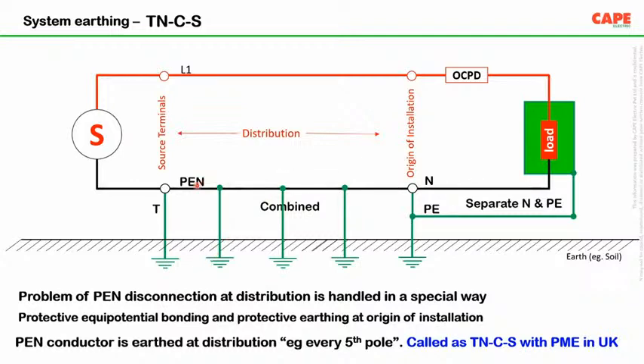So on the distribution, you do this, and at the house, at the building, the meaning of this particular earthing has nothing to do with an earth electrode in soil, but this is the protective equipotential bonding. That means at the meter board, every metallic installation of that particular building has to be interconnected together. Now, in this kind of situation, even if the neutral disconnects at this place, you don't need to worry, because the neutral is connected to earth. The overvoltage or extra voltage coming between the neutral and the earth is controlled. So you can see this explanation in clause 4 of IS 3043.